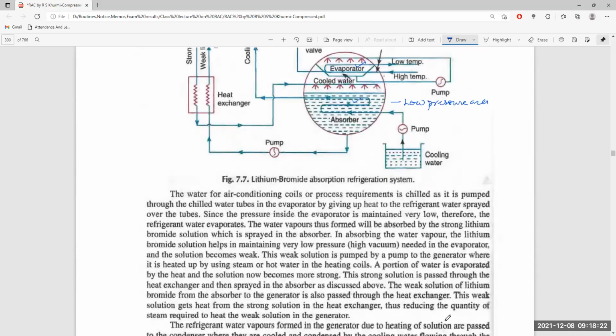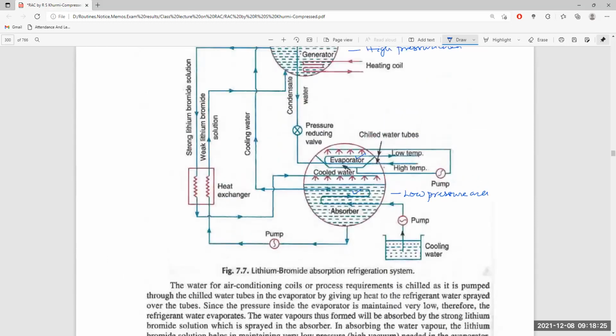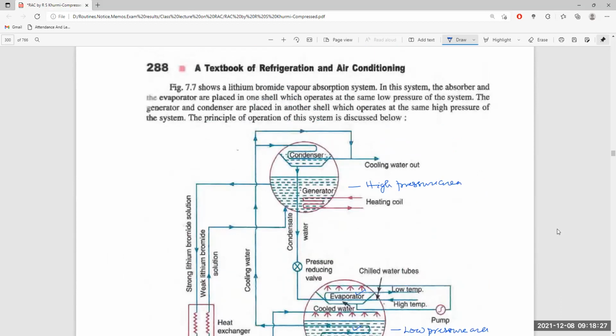What is shown here? Here we have this shell or bulb where it is being heated. The content in this bulb is the water lithium bromide solution. It is being heated up to a certain point through this heating coil. Now, due to this heating, the water vapor forms and goes to the condenser where it is cooled and condensed by the cooling water flowing through the condenser water tube.